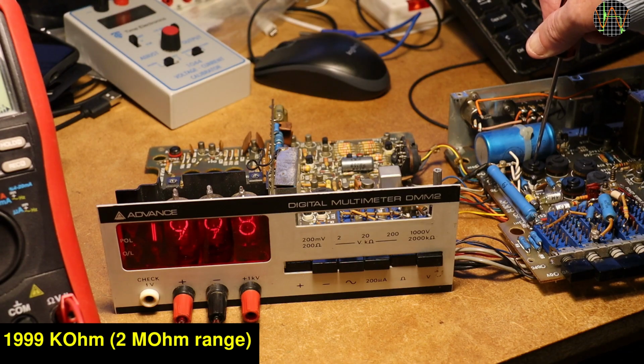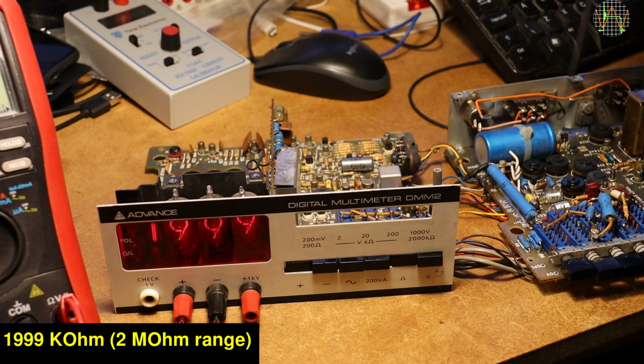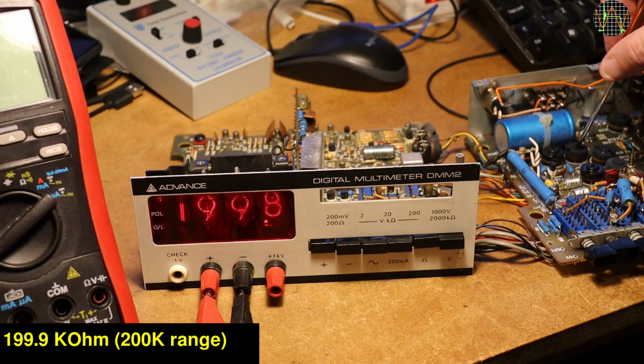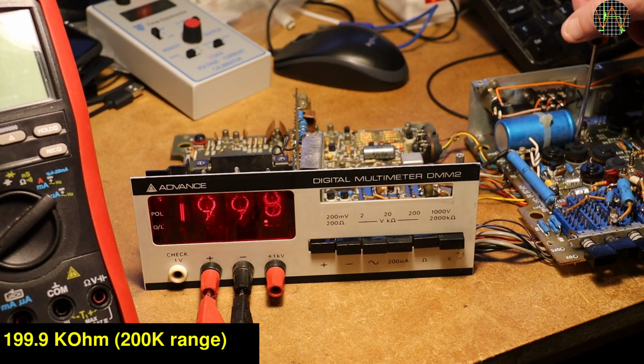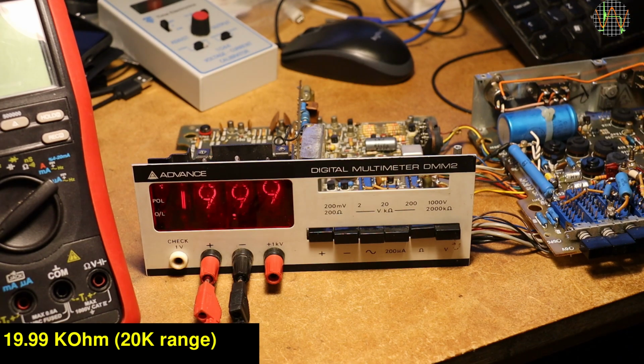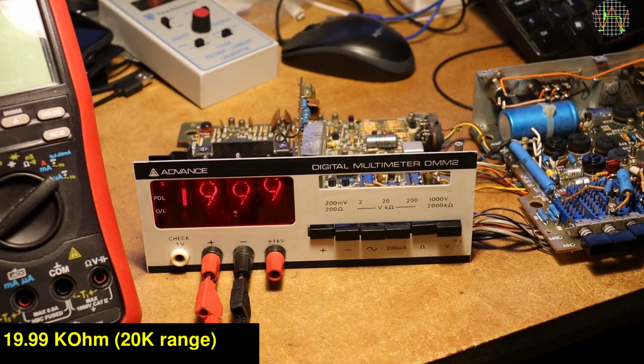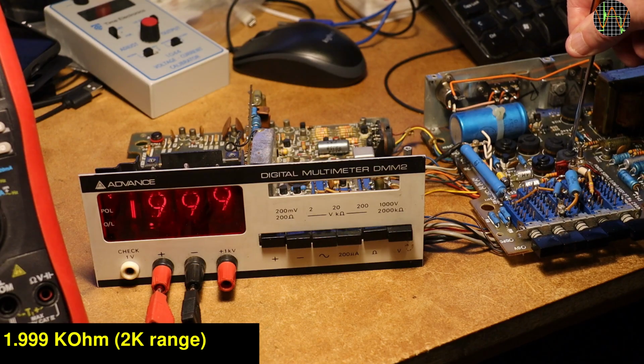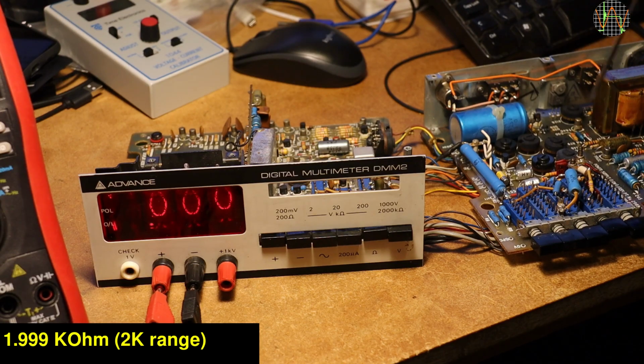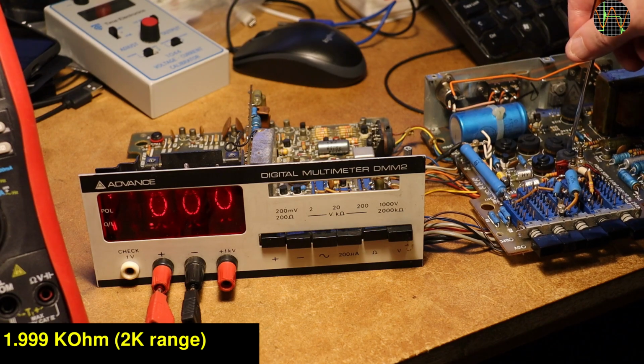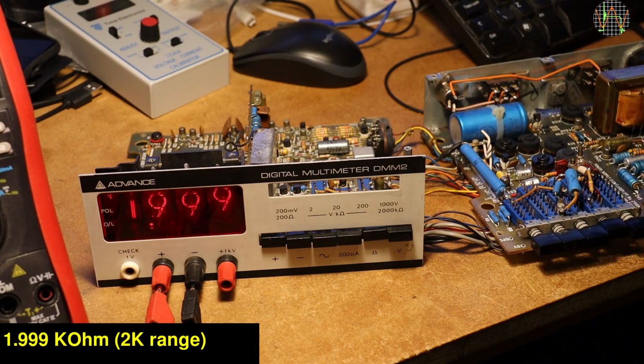Then one must adjust the resistance ranges, starting with a 2 meg range and going down to 2K. I show this part much accelerated as it's actually quite cumbersome, because you need of course matching reference resistors like 1.999 meg, 199.9K and so on, which means you have to use resistor decades to dial those unusual values in.